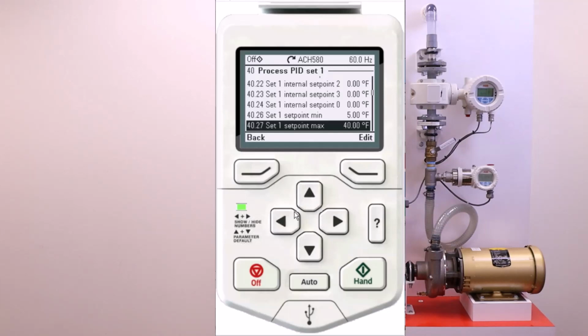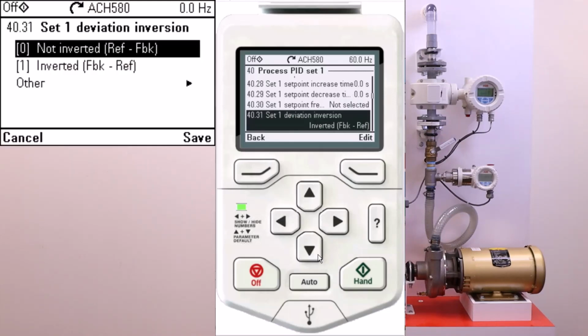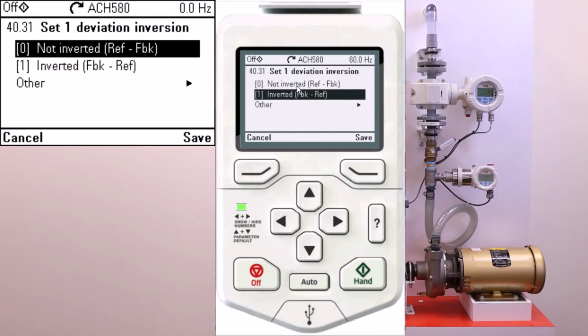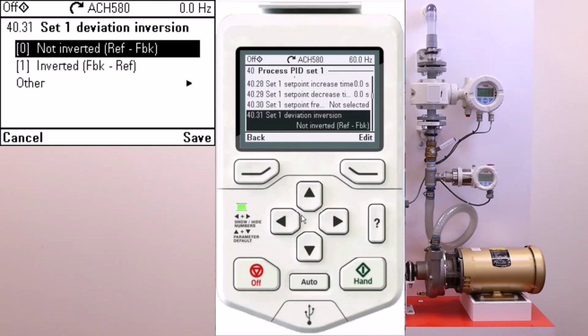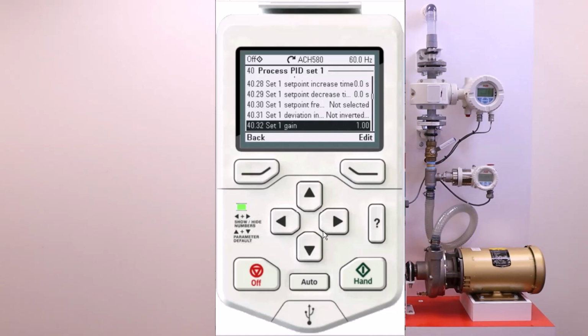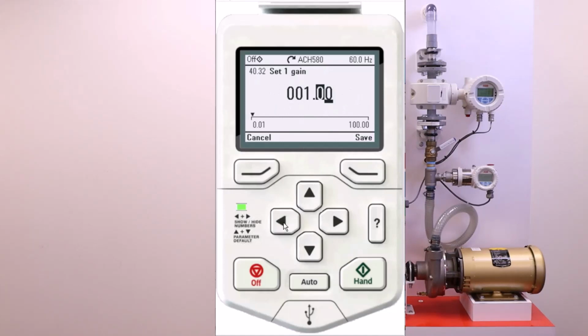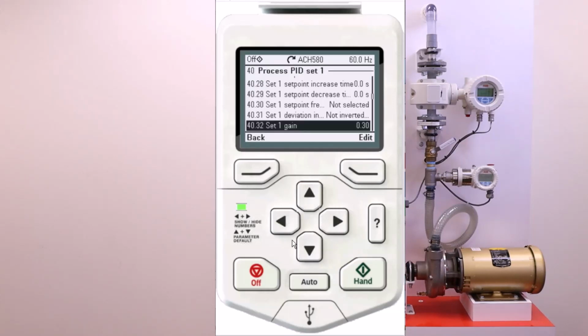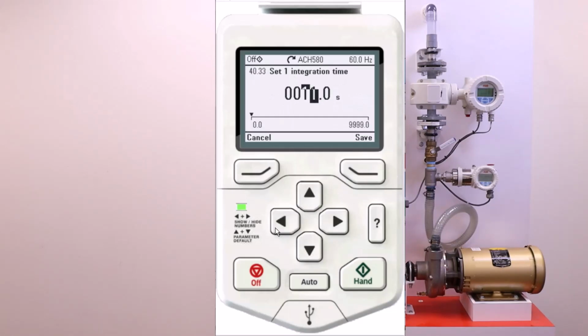We need to look at how we're going to bring our feedback into our system. And that is 31. We are not going to be inverted. So we're going to have our feedback directly from 8005. So it's going to be not inverted. Save. And I'm going to need to add a little bit of gain to my system. Actually, a little bit less because of my system the way it is and the size of it. So we are going to put it at 0.3, save. And our integration time is only going to be 1 second because of our fast response time that we have on this small unit.